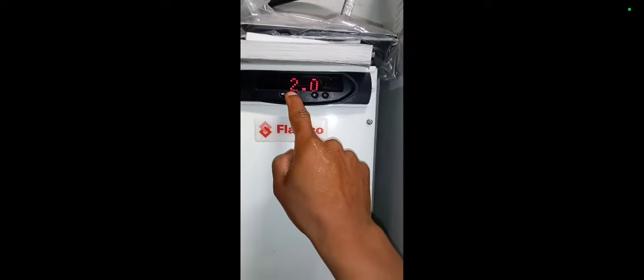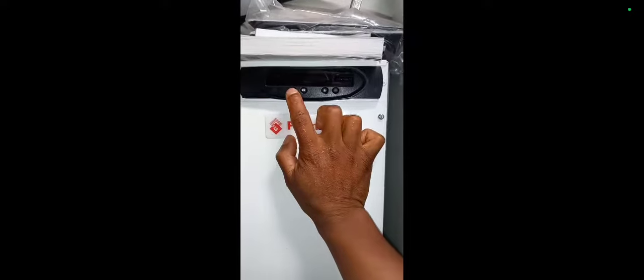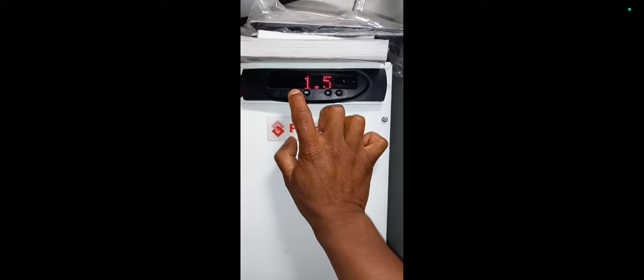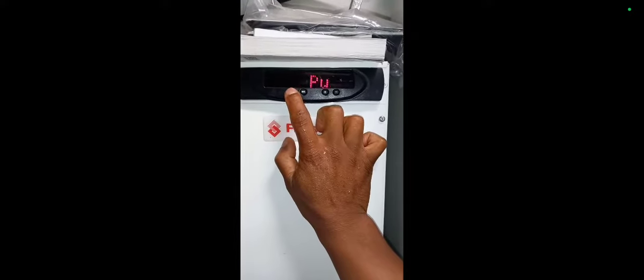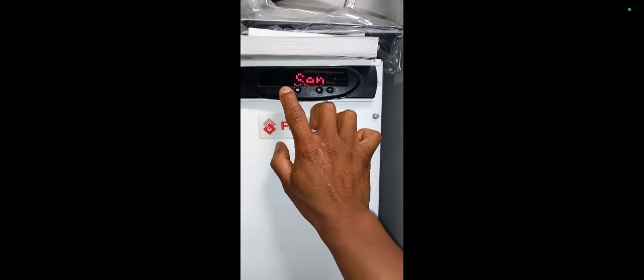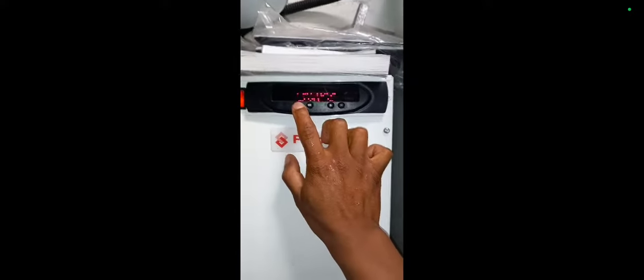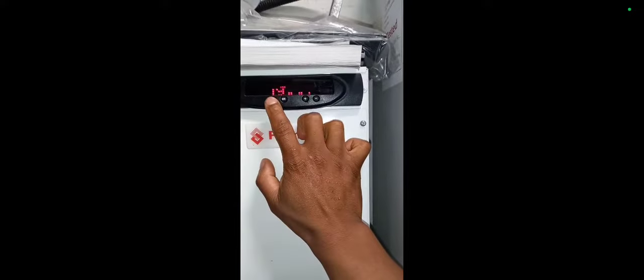You can see the system there has flagged up an issue because I've jumped into the PU. So I'm hitting the minus button there once I've got into the settings, and that is testing pump 1. If there was another pump, you'd hit the other button here, and then that would test the other pump. You'd hold it down. But now I'm just hitting the set button rather than holding it down to go through the different settings, and then the pressurization unit will be satisfied and tell the BMS to be satisfied. Here we go. System's all fine now.